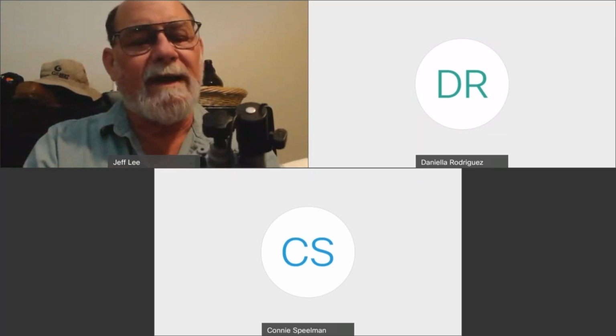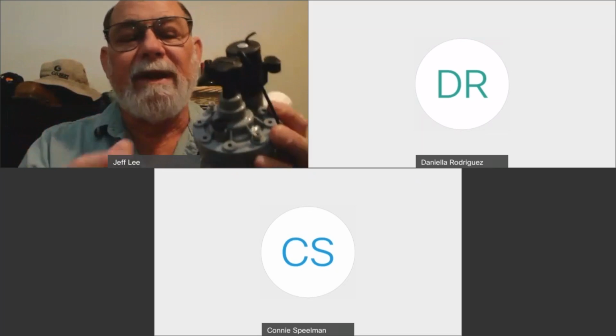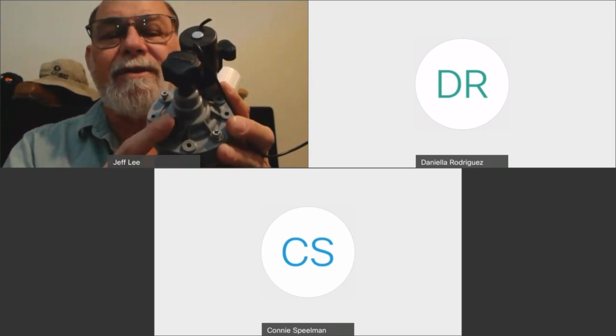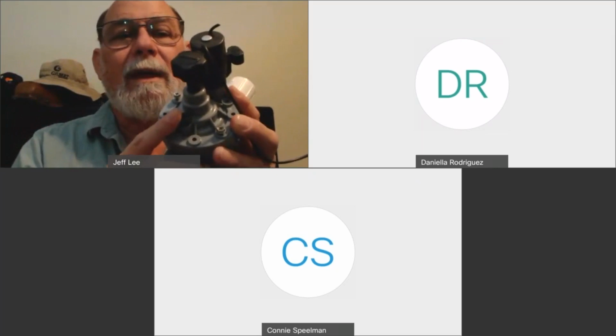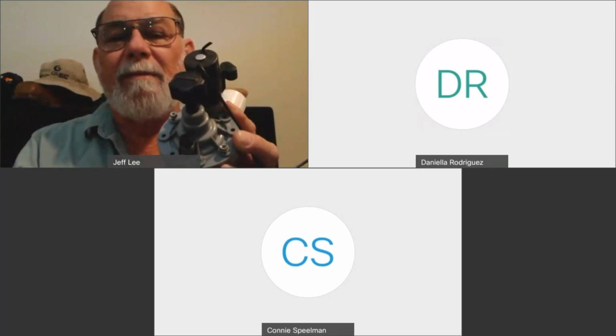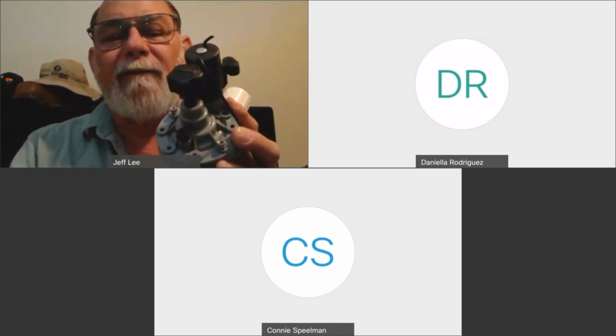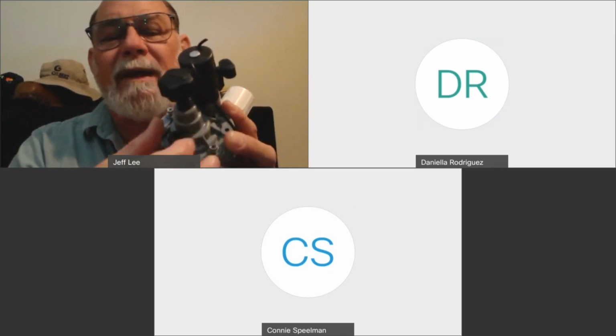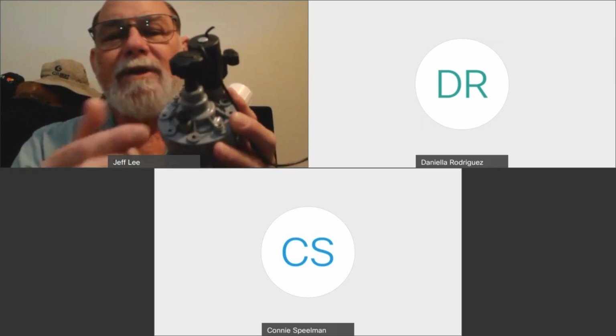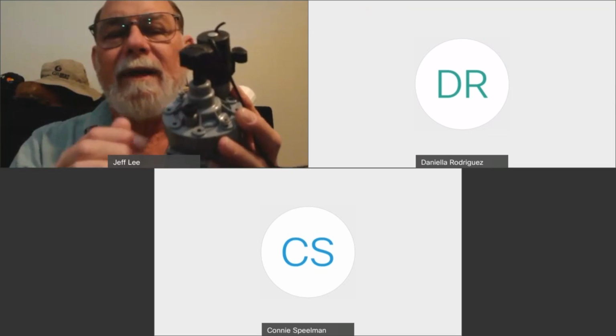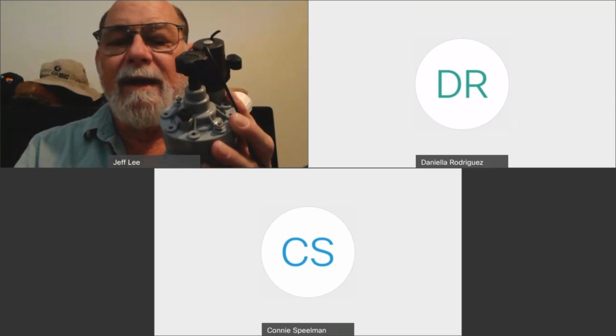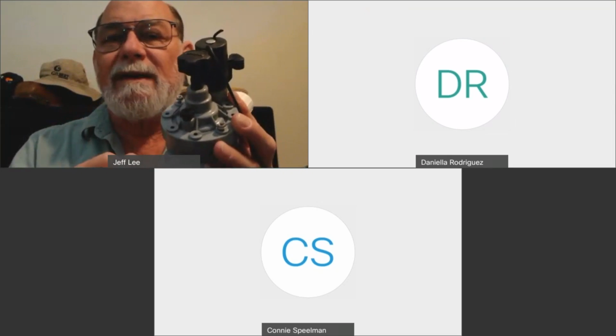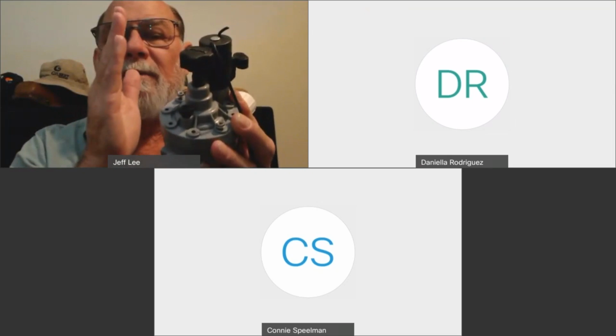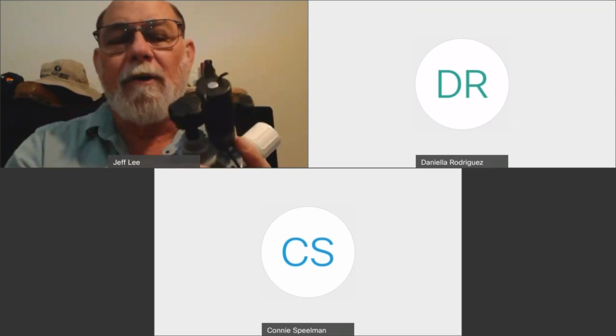Many of your valves, even if they have what we call that internal bleed, they also have an external bleed screw here, this little black screw. If your valve doesn't have the ability to open up by turning the solenoid, it definitely will have one of these. And what we do is we open that up about one turn, and you'll see water kind of spitting out of there. We call that an external bleed. That again relieves pressure above that diaphragm. Now the water underneath there can push it open and the water goes out.